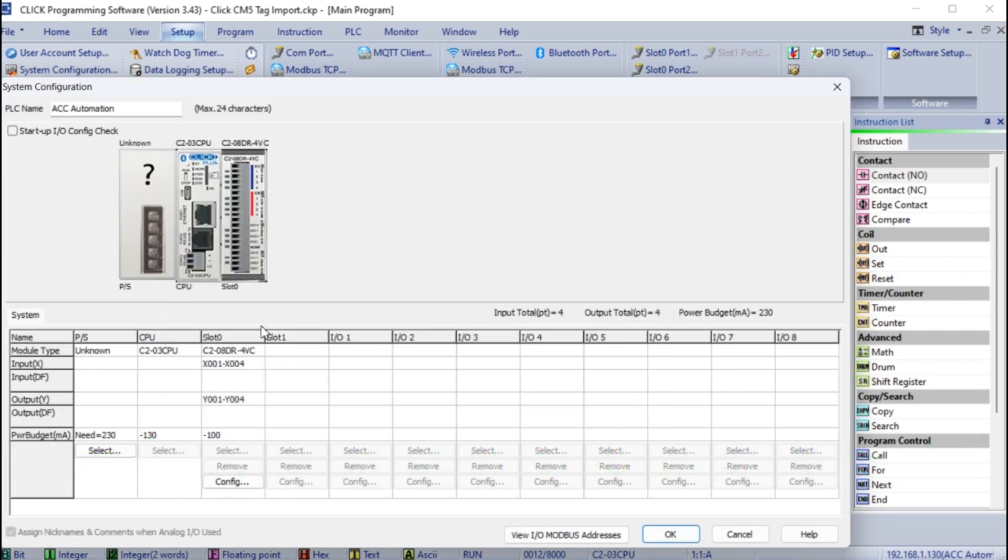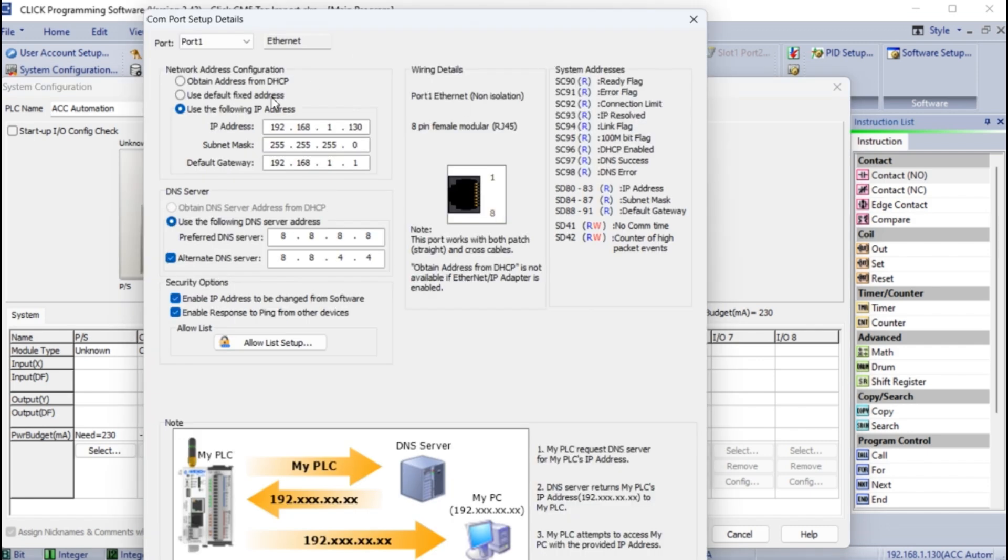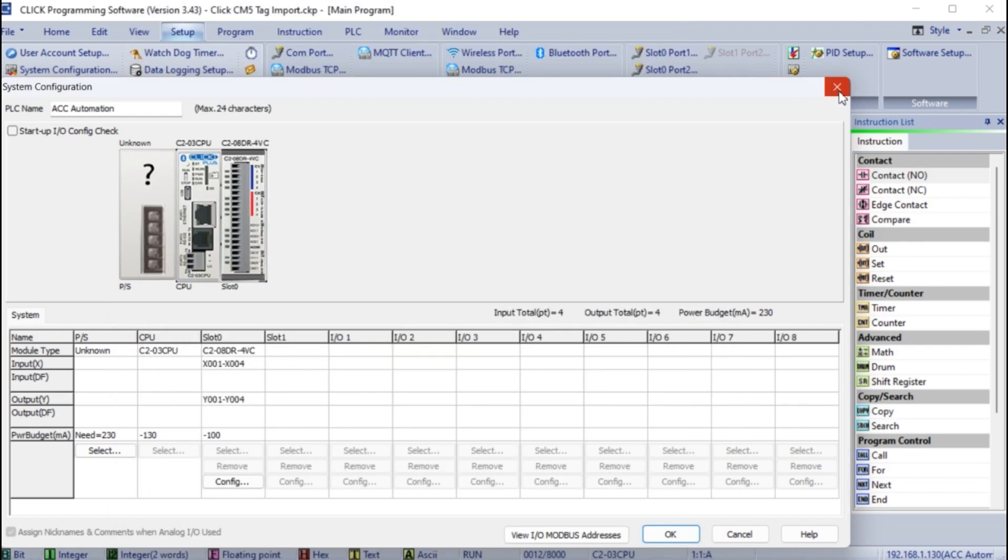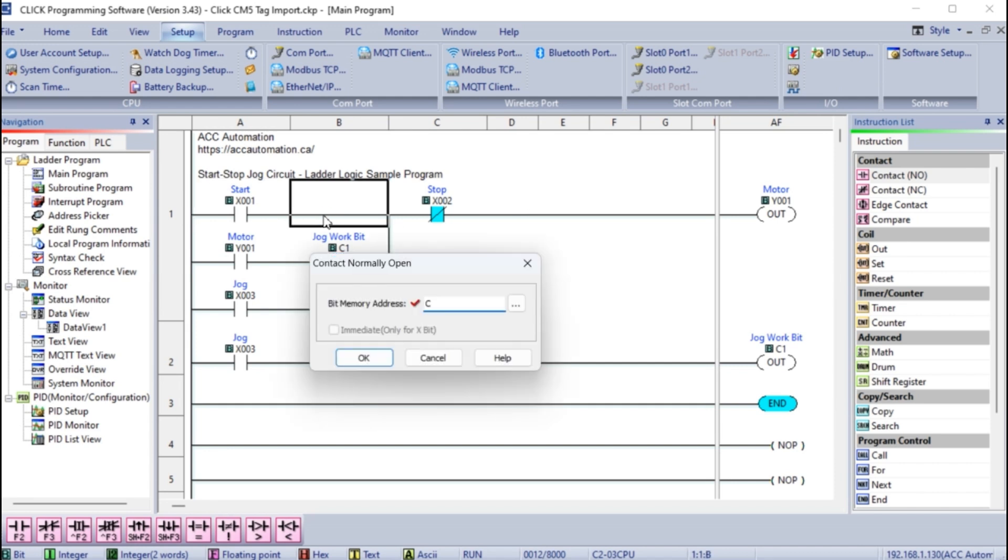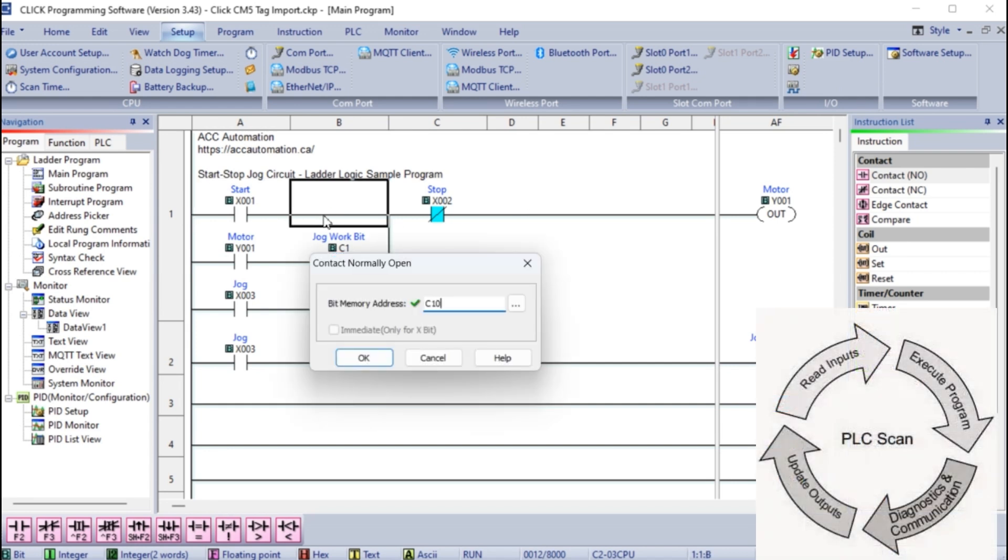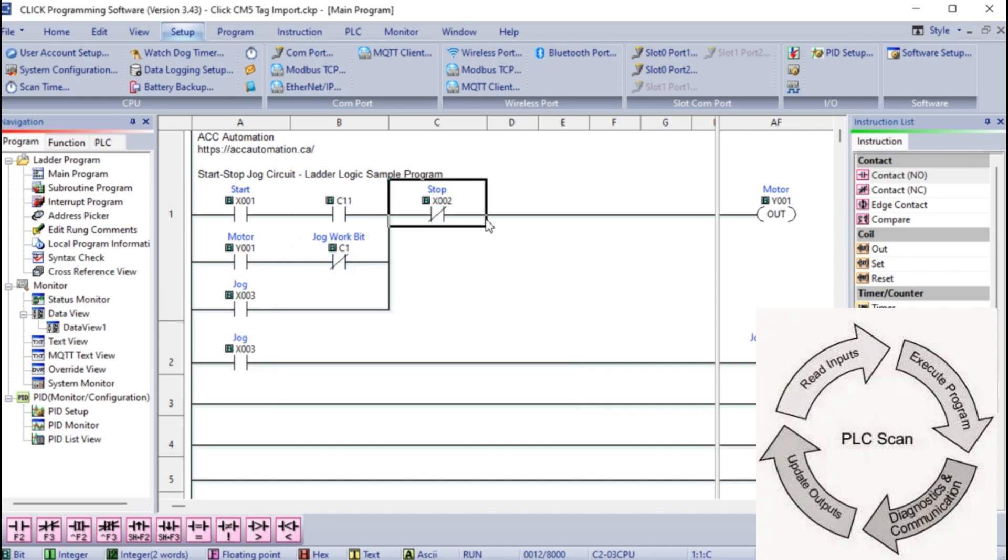Select the system configuration to see the physical inputs and outputs. A common mistake is to assume that we can change the physical inputs and outputs of the PLC with the HMI. The PLC constantly scans the logic, updates the physical inputs and sets the outputs.